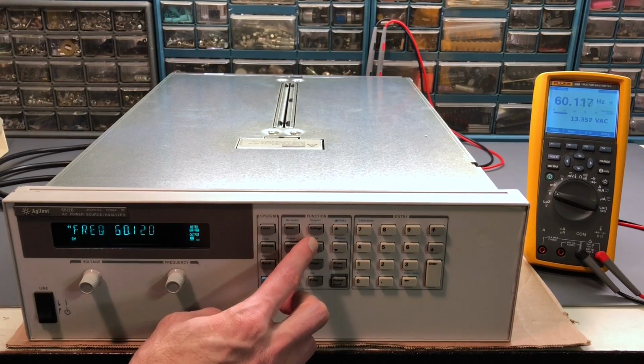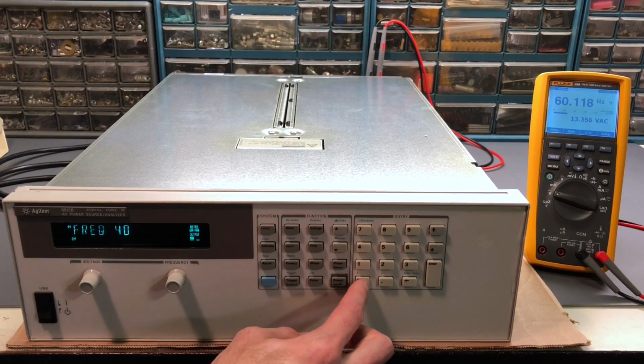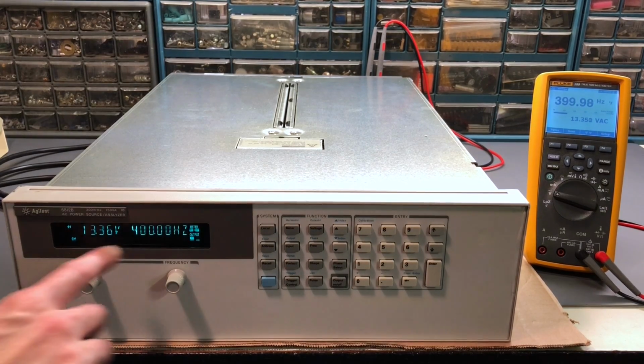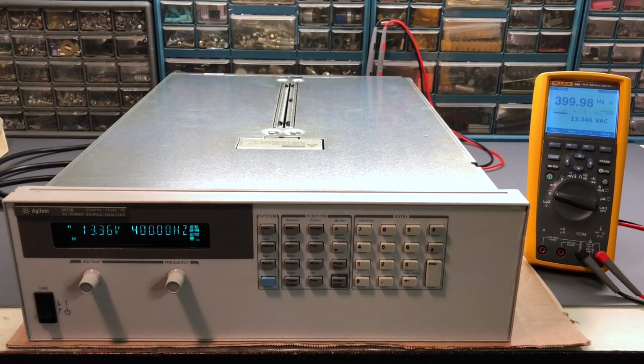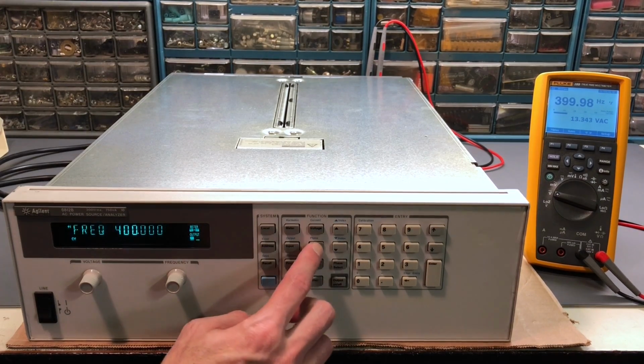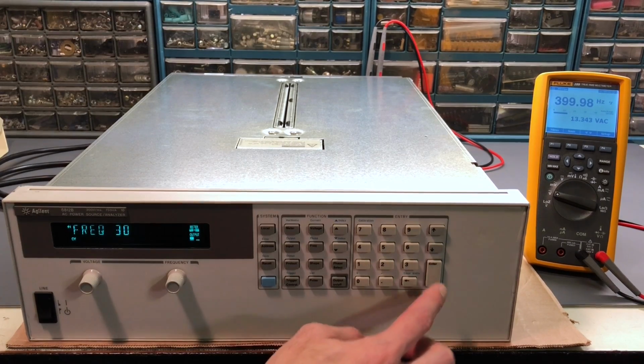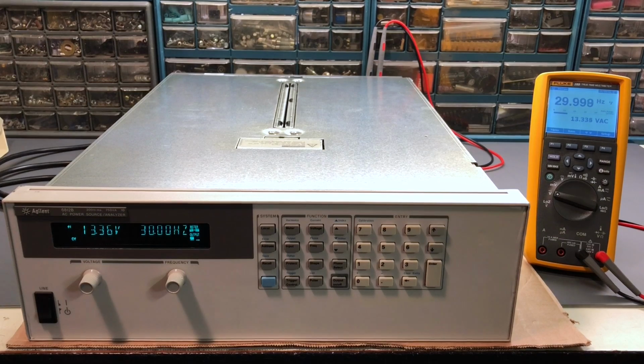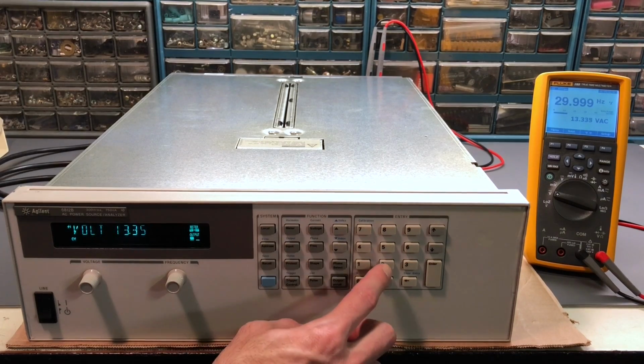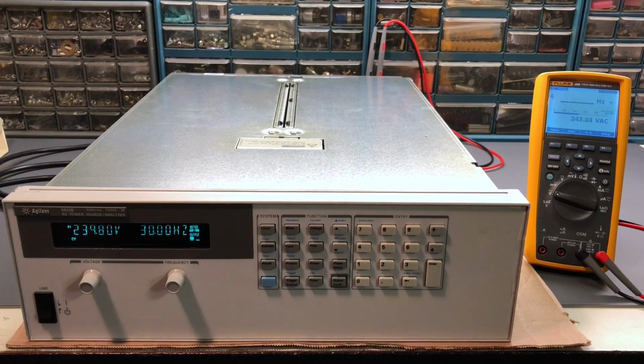Let's try frequency. Let's make this something like, let's say, 400 hertz. So 400 hertz, 400.00. And the display over there, 399.98. No issues with that. Let's try something really low. Let's try, like, say, 30 hertz. No problem there. 29, 30 hertz on the display, no issues. Let's increase the voltage. Let's try something like, say, 240 volts. Okay, very nice. So this is 239.8 and 239.78 on the digital multimeter. So really looking good at this point. No issues with how it's performing.